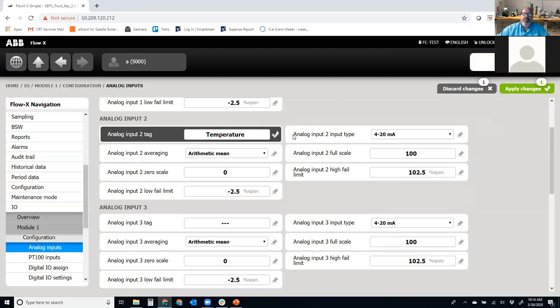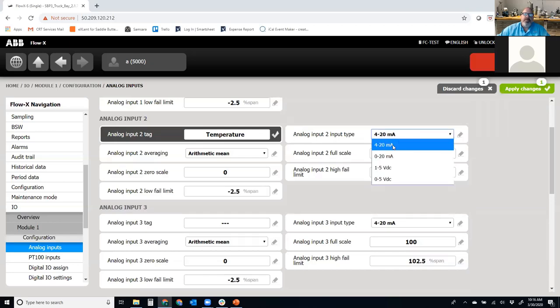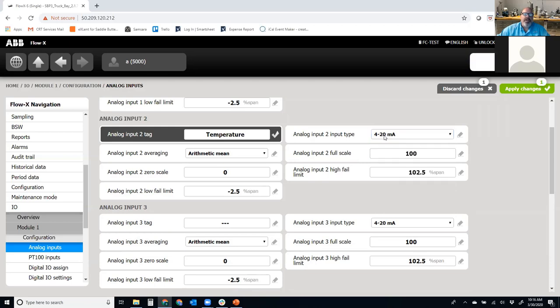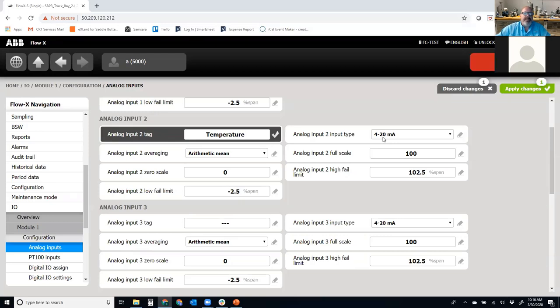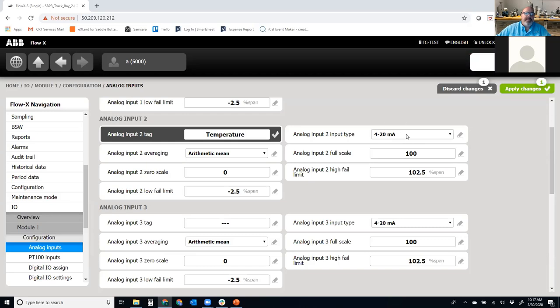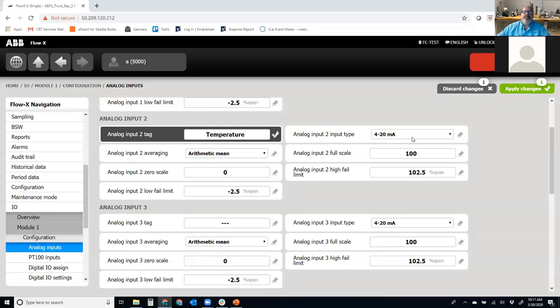I'm going to go into analog input number two and I'm going to put a tag in here. The tag is solely to let me know what this is going to be used for within the system. So temperature. Now on this analog input, it can be a few different things. It can be four to 20, zero to 20, one to five volts DC, or zero to five volts DC. We're going to keep it at four to 20 milliamps.